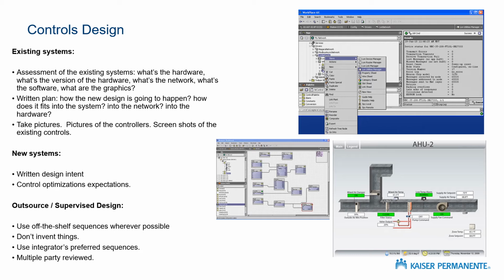We want to see a plan that's written out for how the new design is going to happen, how it fits into the existing control system, how it lands onto the network, what pieces of hardware are getting added or what points are getting added to the existing pieces of hardware. Big tip is to take pictures. Take pictures of the controllers, take screenshots of the existing control system. And I am not at all kidding. Pull out your phone, shoot a photo of the air handler screen, crop it, and drop it in your basis of design. That at least tells us that you've been in the same room as that computer, and it shows us what points are mapped onto that air handler screen, which is insanely important.